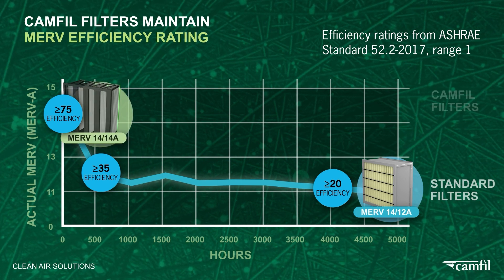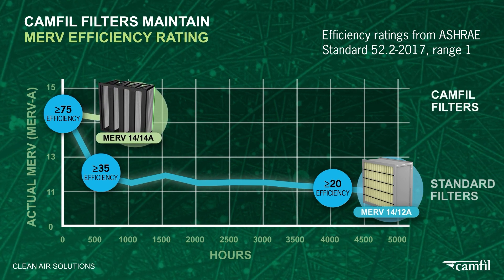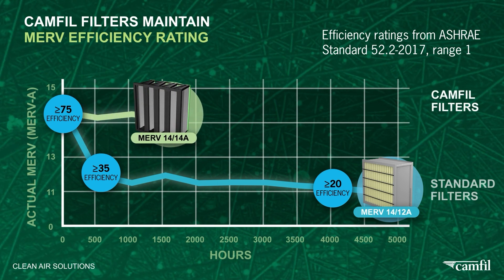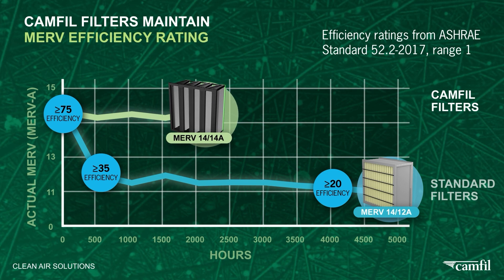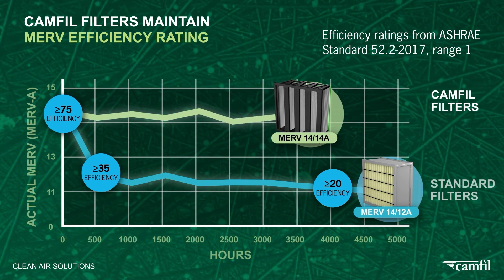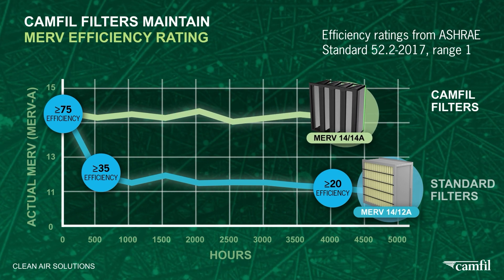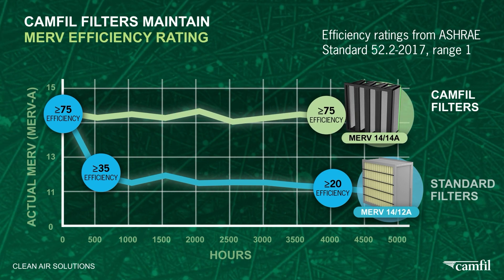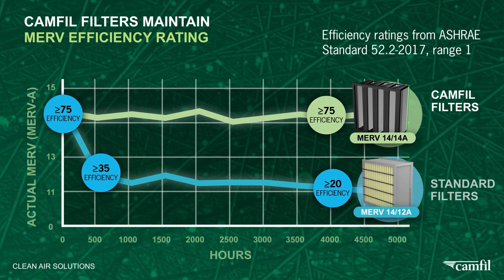In contrast, the green line representing the fine-fiber MERV-14 filter maintains its original particle capture efficiency for its entire service life.